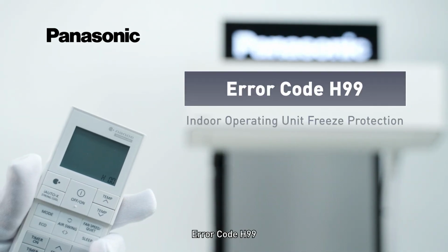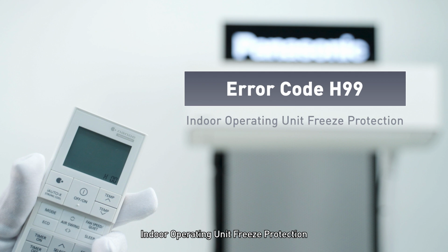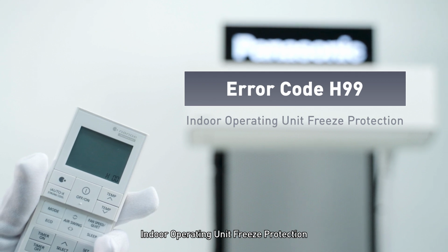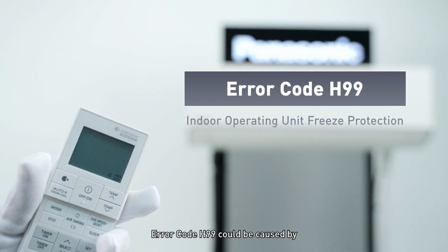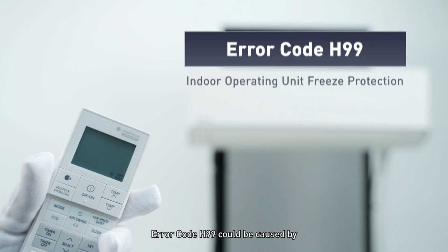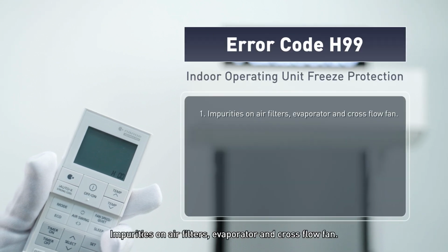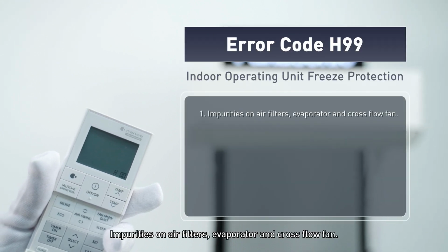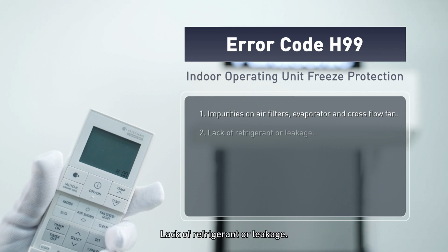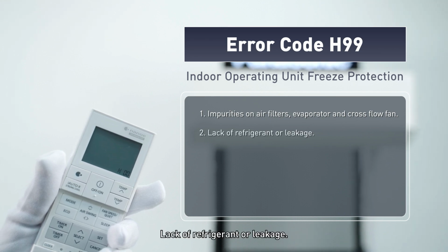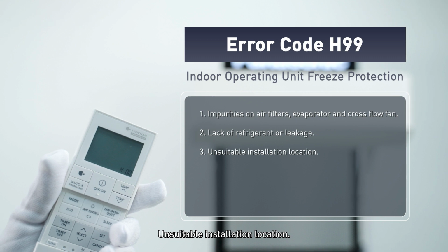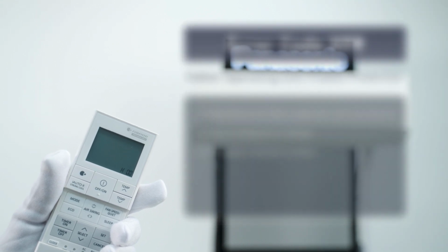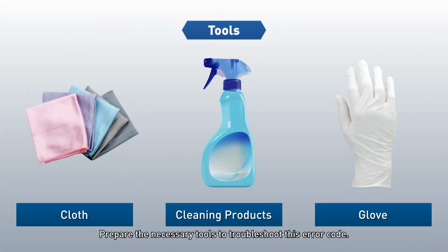Error code H99. Indoor operating unit freeze protection. Error code H99 could be caused by impurities on air filters, evaporator and cross-flow fan, lack of refrigerant or leakage, unsuitable installation location. Prepare the necessary tools to troubleshoot this error code.